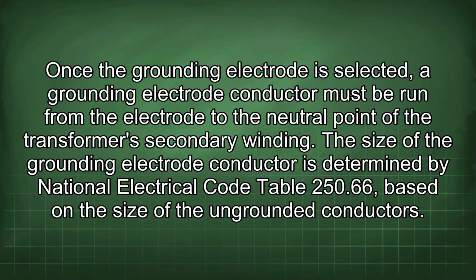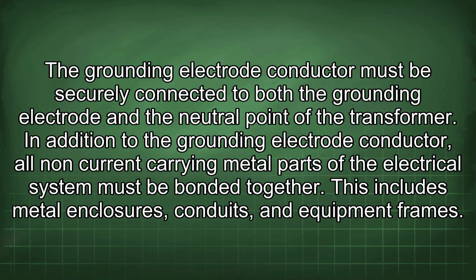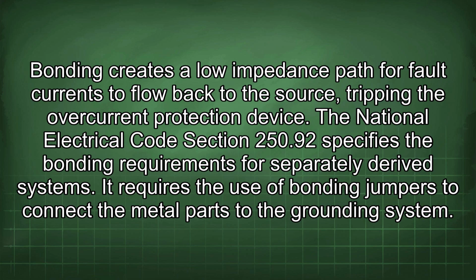Once the grounding electrode is selected, a grounding electrode conductor must be run from the electrode to the neutral point of the transformer's secondary winding. The size of the grounding electrode conductor is determined by National Electrical Code Table 250.66, based on the size of the ungrounded conductors. The grounding electrode conductor must be securely connected to both the grounding electrode and the neutral point of the transformer. In addition to the grounding electrode conductor, all non-current carrying metal parts of the electrical system must be bonded together. This includes metal enclosures, conduits, and equipment frames. Bonding creates a low impedance path for fault currents to flow back to the source, tripping the overcurrent protection device.